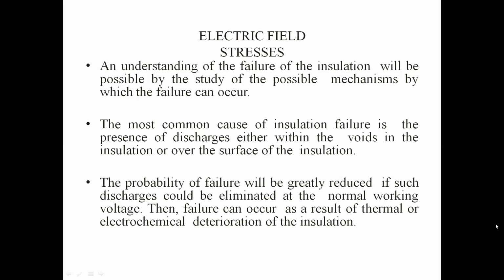The most common cause of insulation failure is the presence of discharge, either within a void in the insulation or over the surface of the insulators. Probably this type of thing can be avoided. If these voids can be avoided, then the normal working voltage is well and good. If these voids are not cleared at the normal working voltages, then it creates a problem. Then the failure can occur, which results in thermal or electrochemical deterioration of the insulation.